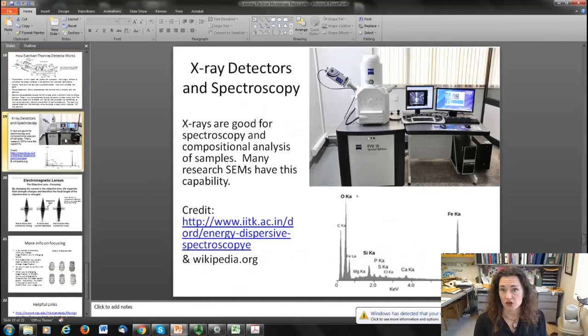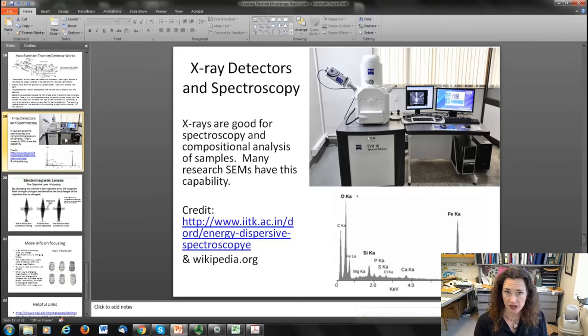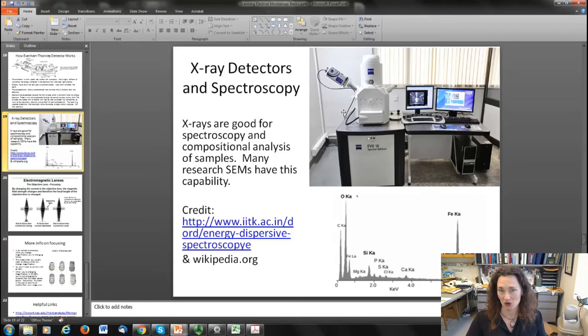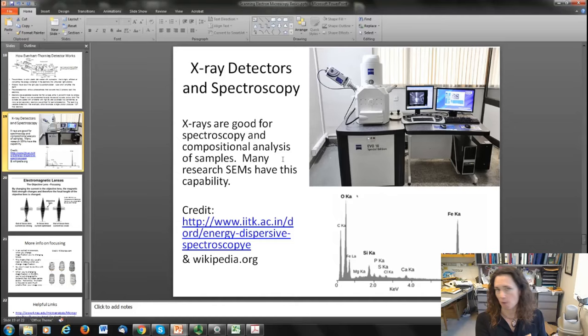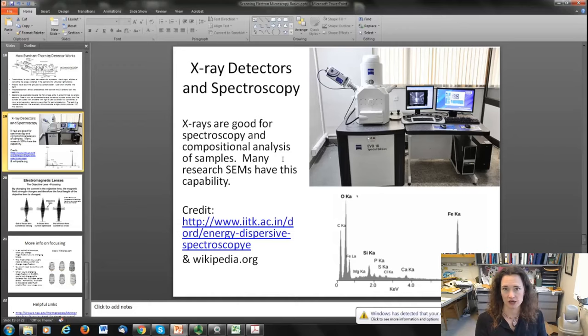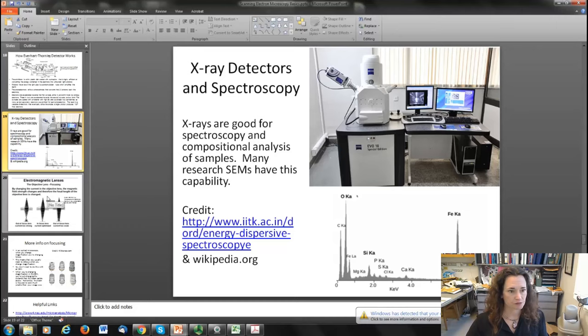X-ray detectors are also really common on many research scanning electron microscopes — they're great for spectroscopy and compositional analysis of your samples. They're pretty easy to identify because they're large things hanging off the side of your SEM. X-ray spectra typically show peaks that have been catalogued from various elements, and so you take a spectrum and have your software automatically identify the peaks. For example, a peak at a certain energy is an oxygen K-alpha peak, and a peak at another energy is an iron K-alpha peak, allowing you to compositionally identify your sample.